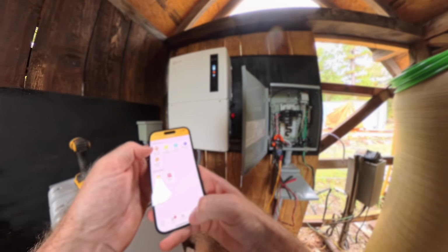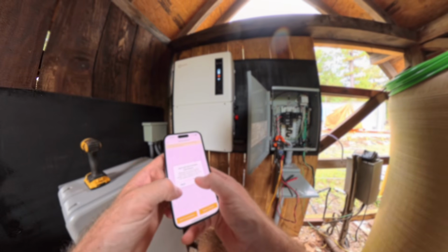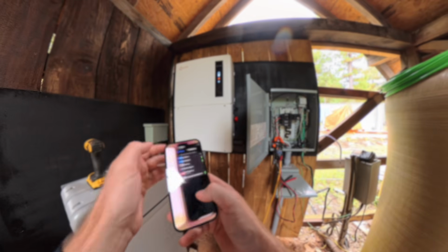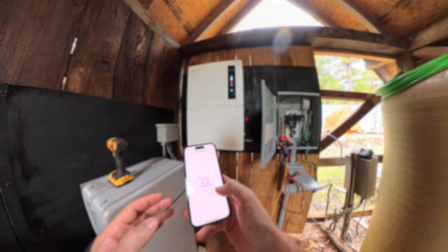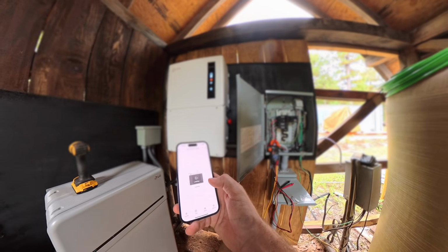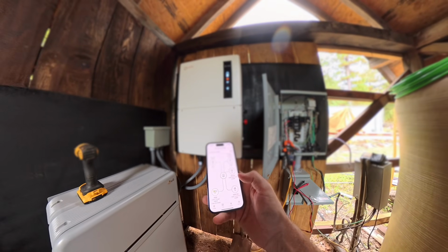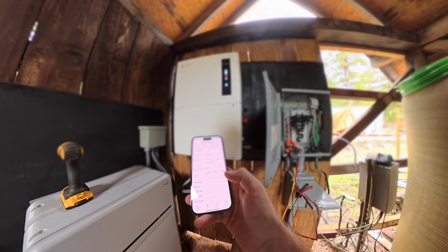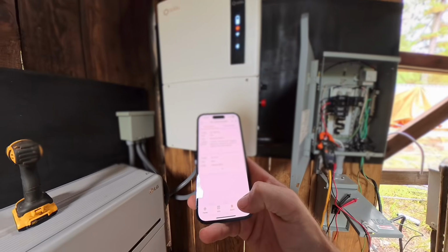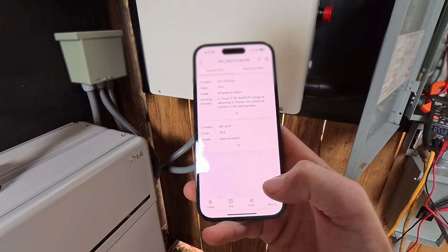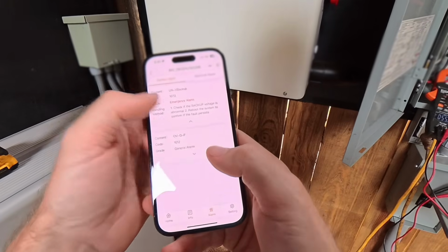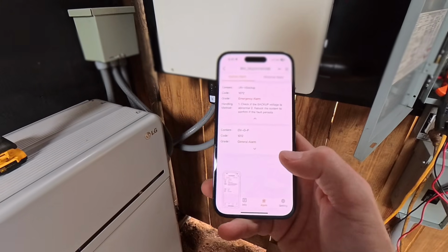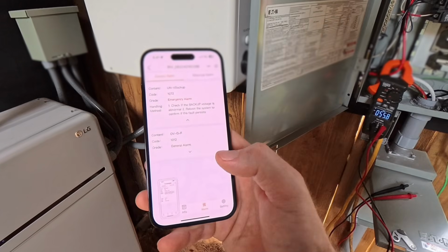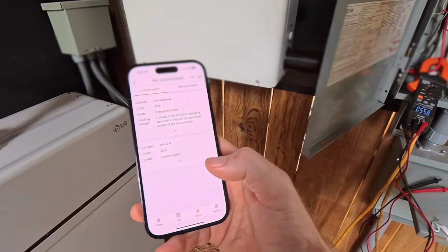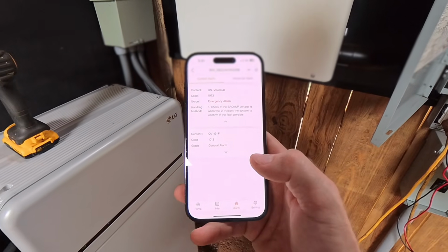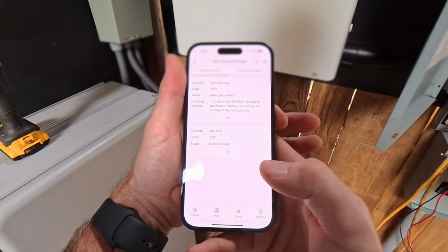I'm going to go to Services, Local Debug, Bluetooth. I'm not giving it location access, so I hit that, go back, and then go here. Loading. It's turned off. Info. Alarms. Emergency alarm. Okay, UNV Backup, code 1072. Emergency alarm, check if the backup voltage is abnormal. Reboot the system to confirm if the fault persists.